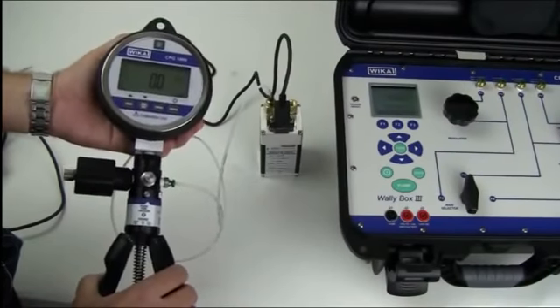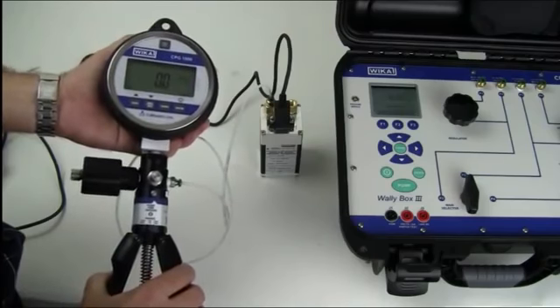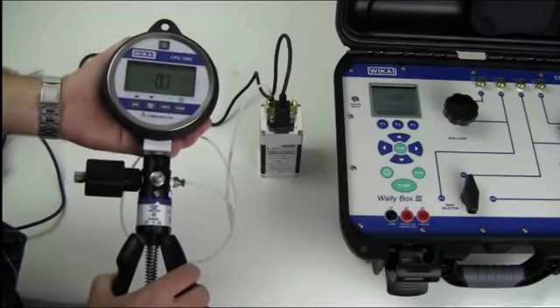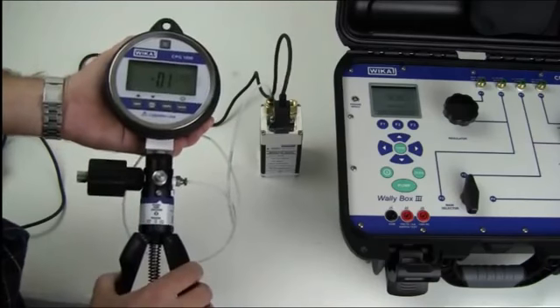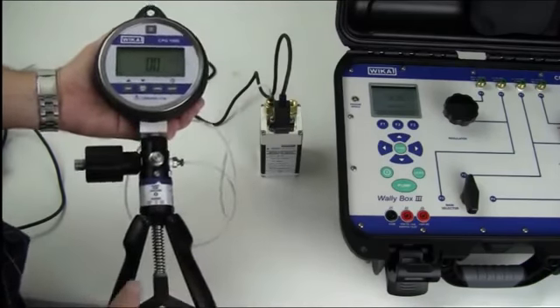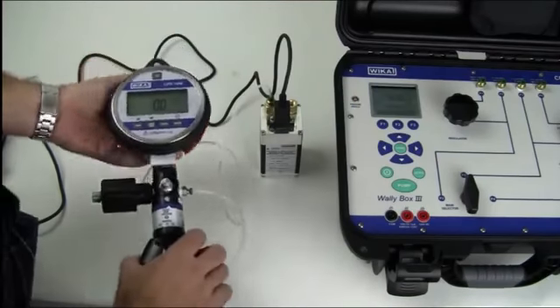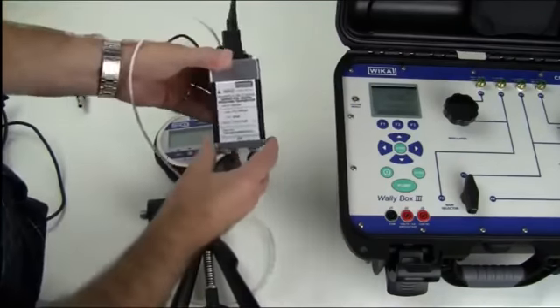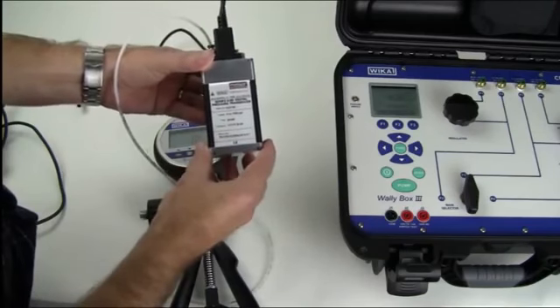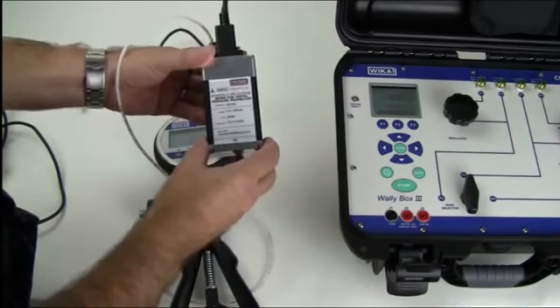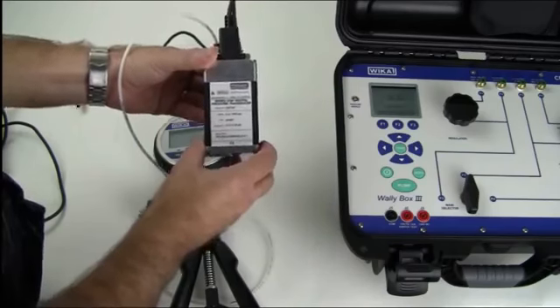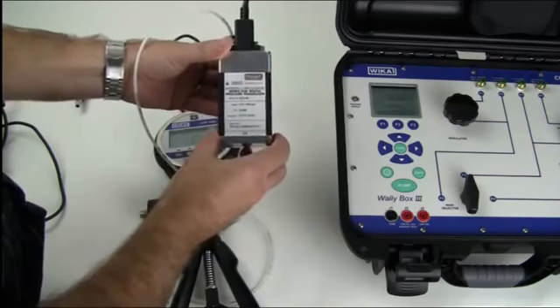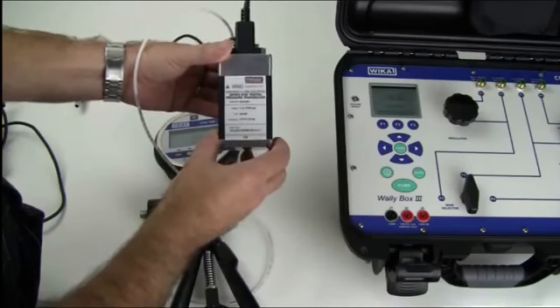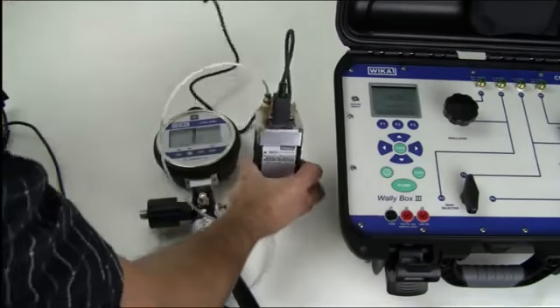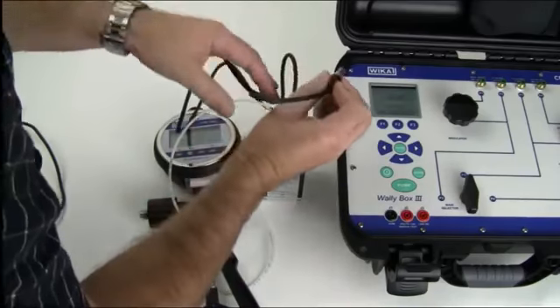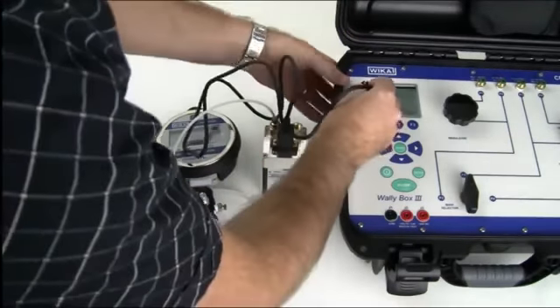Now we're going to calibrate a CPG 1000 WIKA digital pressure gauge. In this case, the pressure gauge goes to 400 psi, but the Wally box only goes to 300. Therefore, to extend the range of the Wally box, we will use an external pressure transducer, in this case the Mensor CPT 6100. This transducer also increases the accuracy of the Wally box, because now we will be 0.01% of reading. We then connect the pressure transducer to the pressure module socket next to the display.